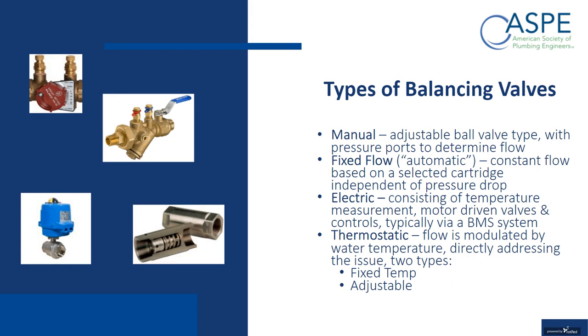Next is electric, which is still not that popular because of the high cost, but it probably is the most effective as far as providing the best results. That consists of a temperature measurement device, a motor-driven valve, and controls. Typically, this type of valve will interface to a BMS, a building management system, or some type of custom controller. Last but not least is what we're talking about today, thermostatic balancing valves. In thermostatic balancing valves, the flow is modulated by the water temperature, so this directly addresses the issue of trying to control temperature. There are 2 types of thermostatic balancing valves on the market: fixed temperature and adjustable.